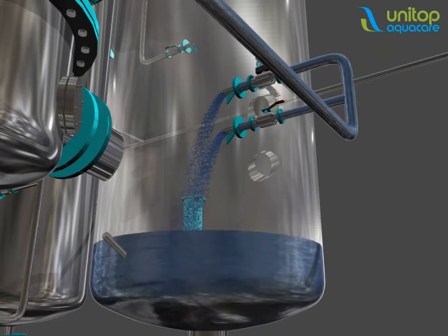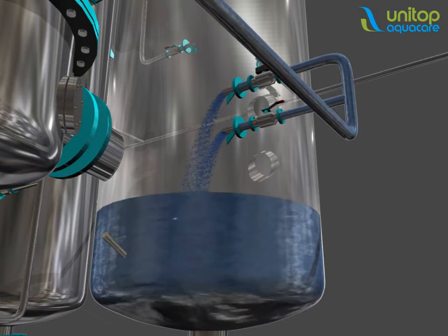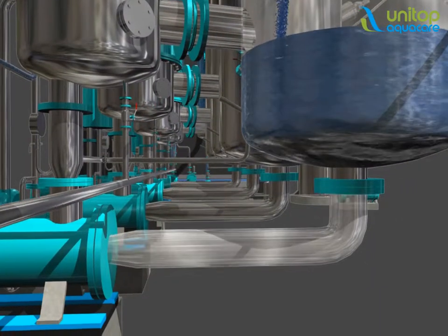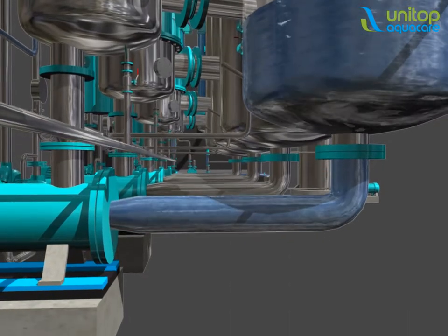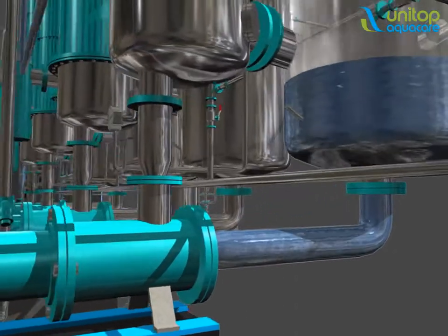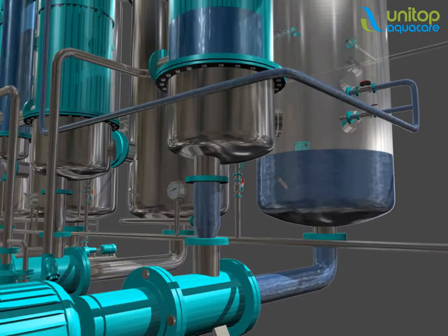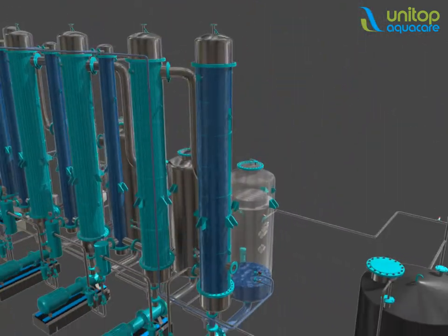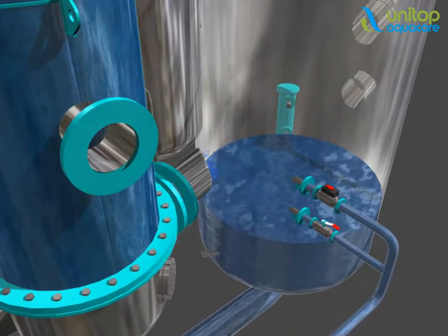Ensuring minimum condensate contamination, the circulation through the heat exchanger is maintained at high velocity with the help of a forced circulation pump, thereby reducing the possibility of scaling in exchanger tubes.